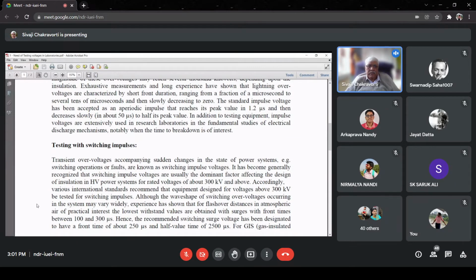What is the difference between lightning impulse and switching impulse? For that, again, we have the standards, that means the national standards. We also have international standard, where the switching impulse waveform has been specified. Basic wave nature is similar, but the time duration is widely different. The lightning impulse is of very short duration, whereas the switching impulse is of much longer duration.